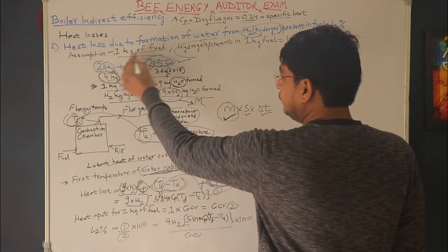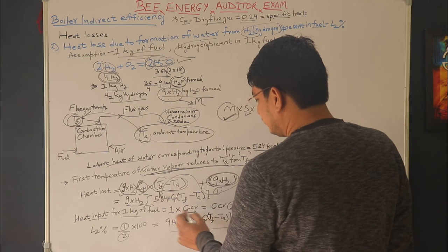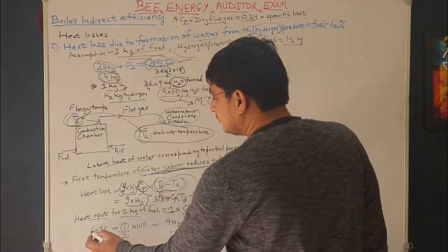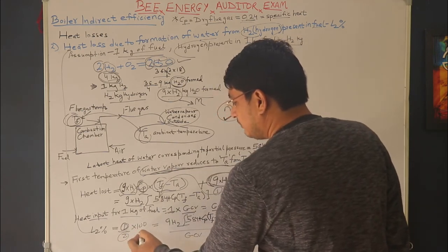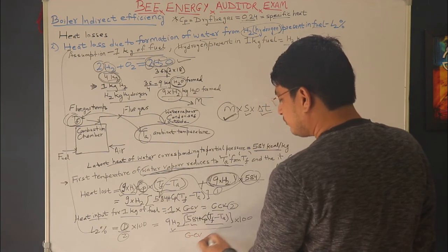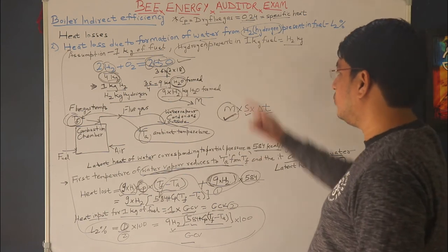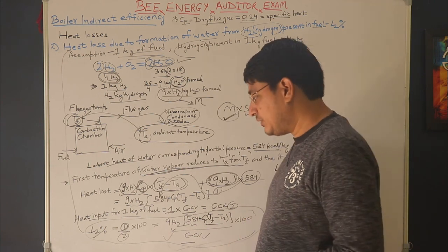Since the heat input for 1 kg of fuel = GCV, the L2% = {9 × H₂ × [584 + Cp × (Tf − Ta)]} / GCV × 100. This is the formula for L2 percent — the loss due to formation of water from hydrogen present in fuel. Understanding the derivation makes it much easier to remember than simply memorizing the formula.